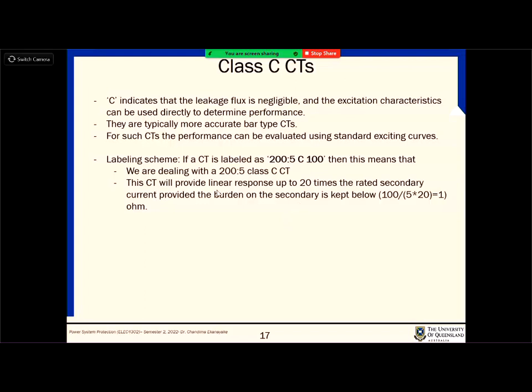100 means the CT will provide linear response, that is basically very low error, up to 20 times the rated secondary current, right? So what is the rated secondary current? In this case, 5. 5 times 20. So the secondary voltage is kept at 100 for the given burden when the secondary current is 20 times its rated current, right? So when the secondary current is 20 times rated current, which means 5 times 20, which is 100 amps. To get 100 volts when 100 amps is going through, you need a 1 ohm resistor. That's what is calculated here.